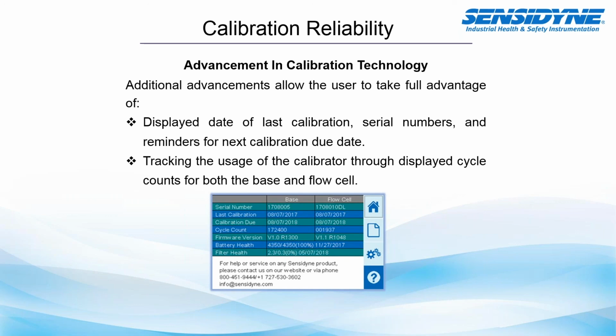Now, tracking the usage of the calibrator through the displayed cycle count can be used for both the base and flow cell. Why is this important? I can actually see how many cycles have been used since my last calibration. The reason this may be important is if I send my unit in for recalibration and I want to see how far back I may have deviated from a desired calibration point, this really shows me how much usage I got over that period.